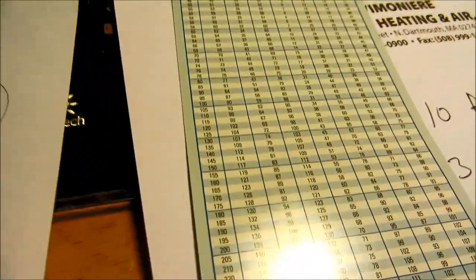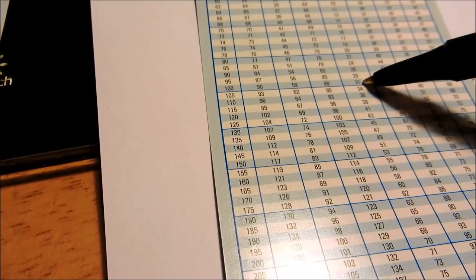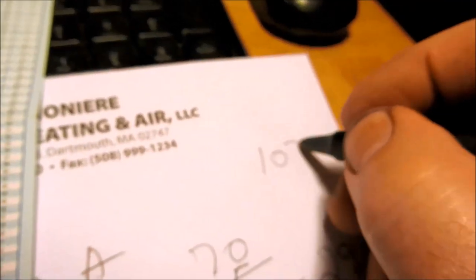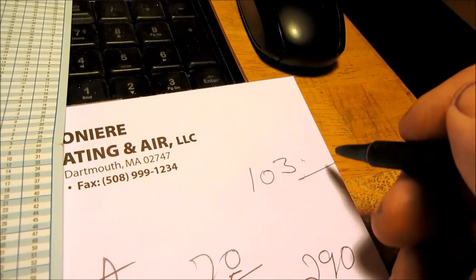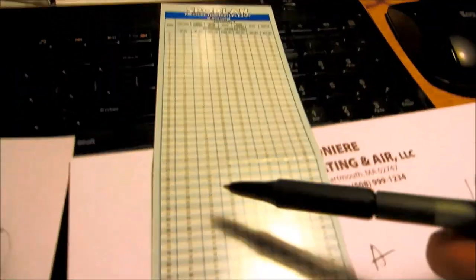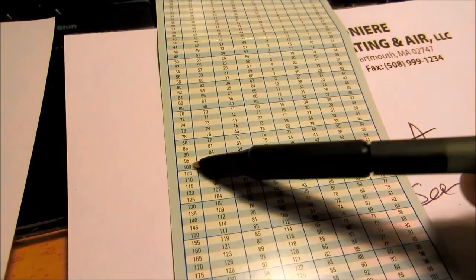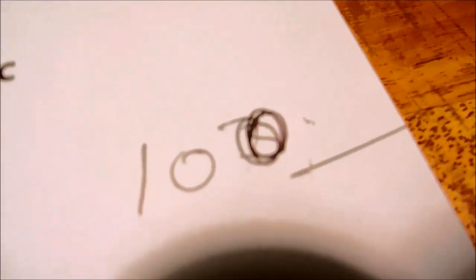58 PSI on R-22 you need to be worried about because you're starting to get into freezing sections. Anything below 100 on 410a, let's see, yeah 100 is 31 degrees. So anything below like 103 on the suction side on 410a you need to really be concerned about that.